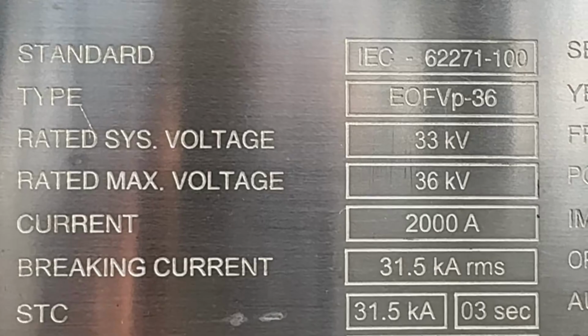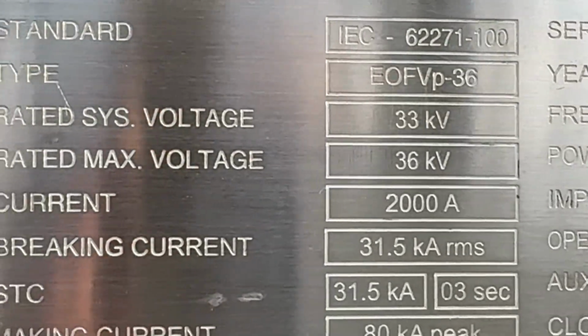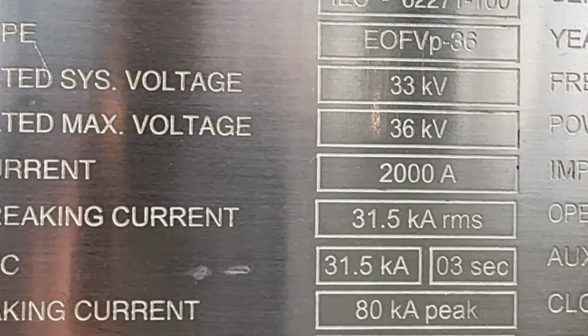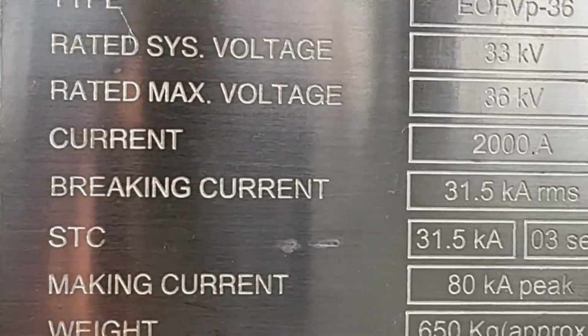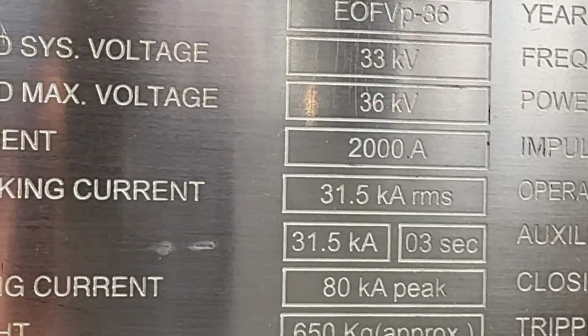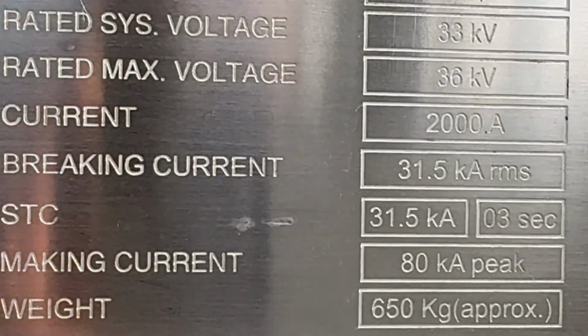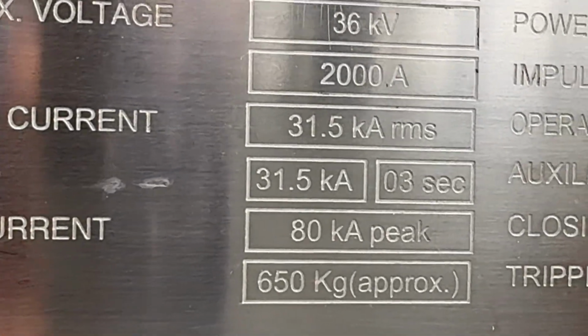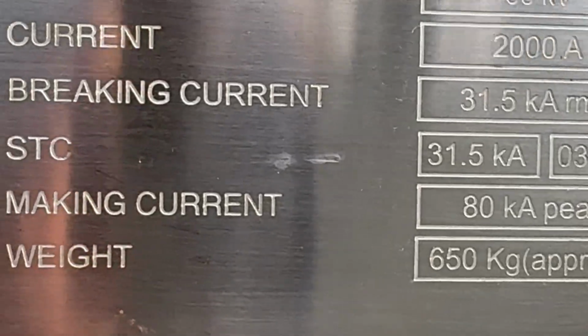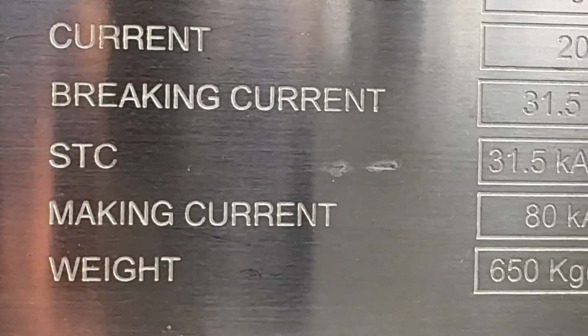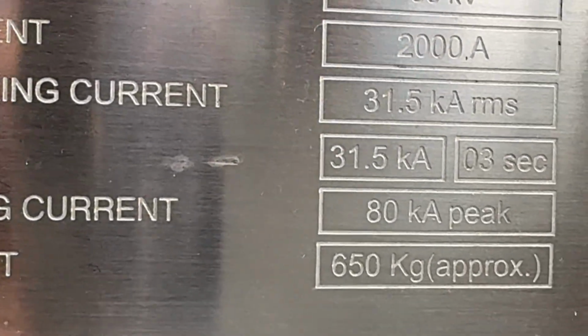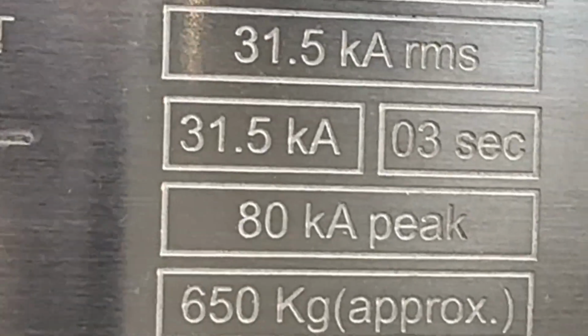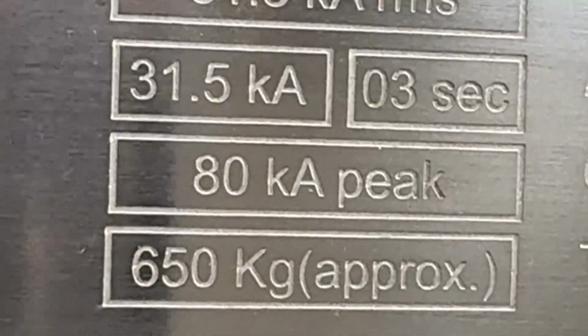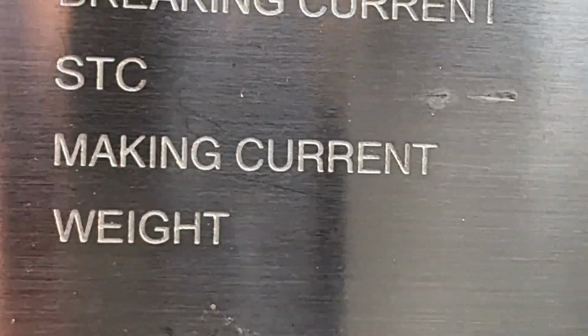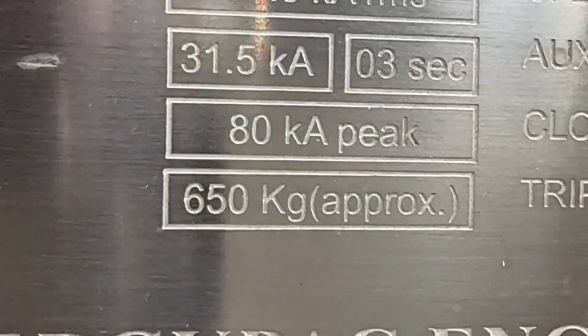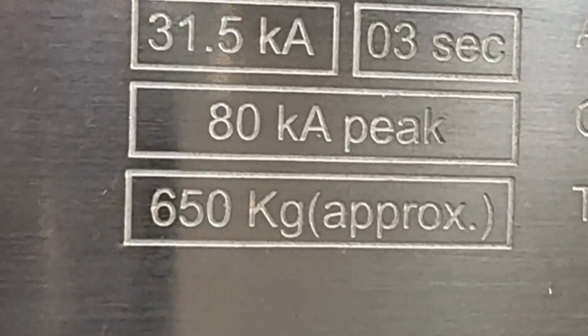Rated voltage, system voltage 33 kV. Rated maximum voltage 36 kV. Rated current 2000 ampere. Breaking current 31.5 kiloampere RMS. Short time capacity 31.5 kiloampere for 3 seconds. And making current 80 kiloampere peak.